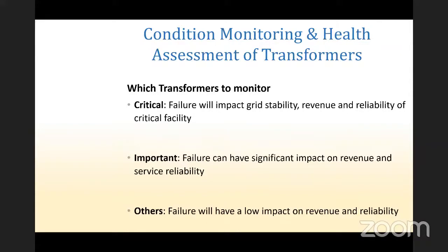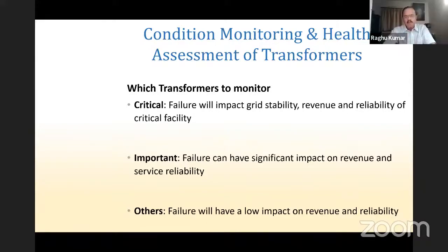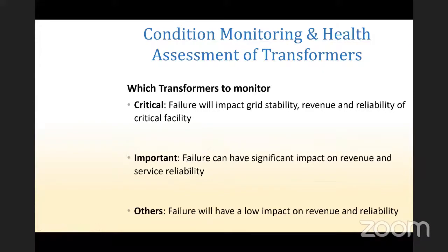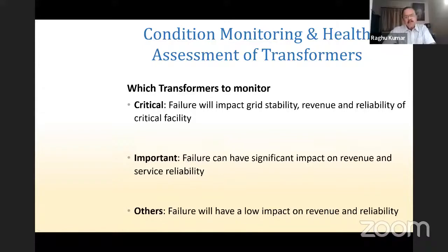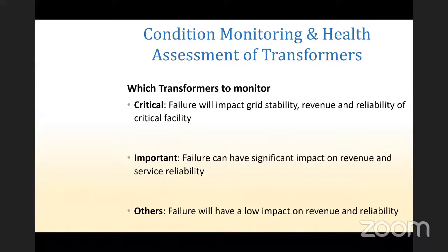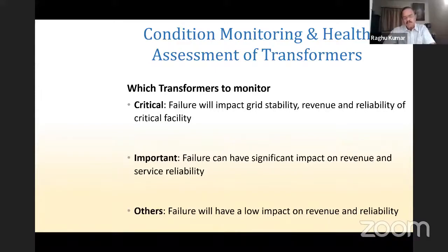So what we were doing is, all transformers which were above 100 MVA were being continuously monitored. And below 100 MVA, transformers were partially monitored. And there are certain below 100 MVA which are fully monitored. Those transformers were the ones which are underground. We had about 12 to 13 underground substations. And all the underground substations are very critical because any fire inside is dangerous. So underground substations are continuously monitored, even if the transformer size is small. And the smaller transformers are rarely monitored continuously. Only offline condition assessments are being carried out on the smaller ones.